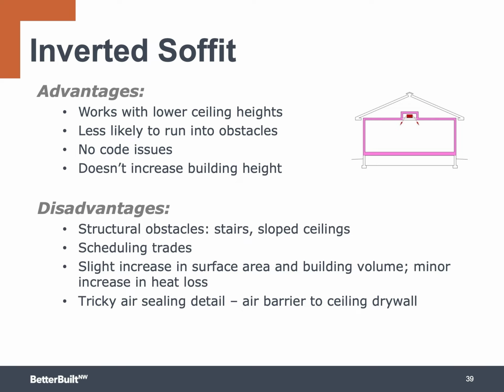An inverted soffit is one way to enclose ducts that would otherwise be exposed in the attic. A rigid box that's usually made of structural sheathing is built around the duct. It's necessary to extend the air barrier from the gypsum board ceiling to the insulated box that covers the ductwork. This approach works well for a central trunk line, but it may become too tedious if the system has a large number of branch ducts. Keeping the branches as short as possible can help. This approach presents few obstacles, but it does require careful planning.